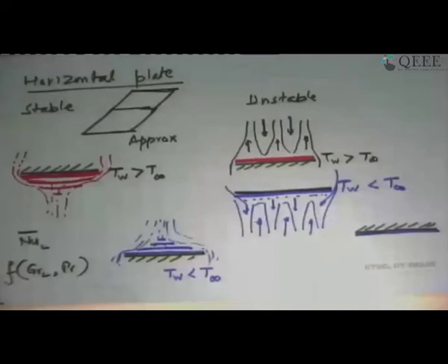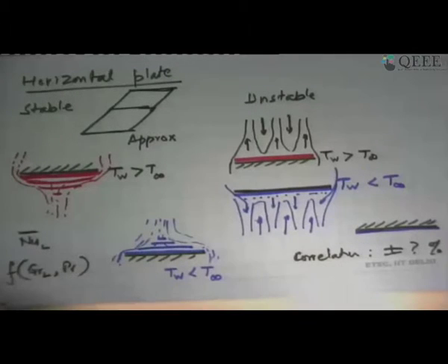So although they are both quite common, it's not so easy to estimate this, and you do have correlations, but then the flow is very unstable, the flow is not exactly predictable, so whatever correlations one may use, there's a lot of uncertainty associated with that. Plus minus 20% is not uncommon.